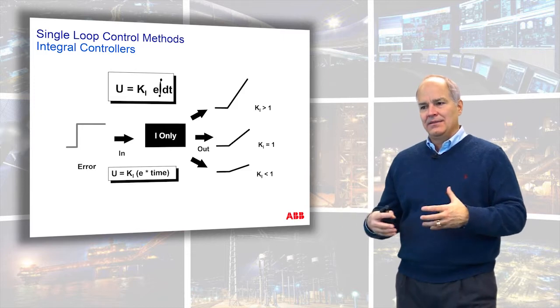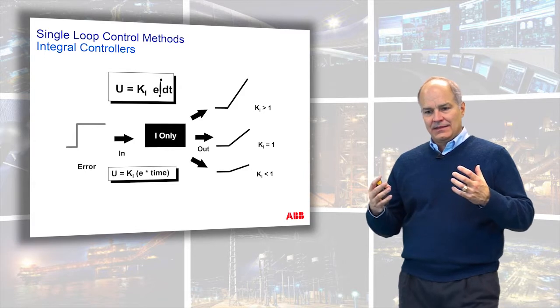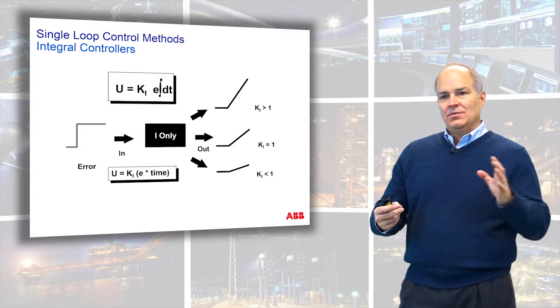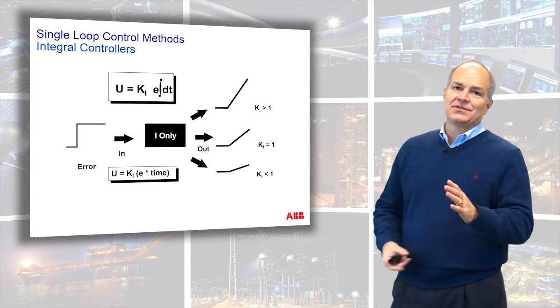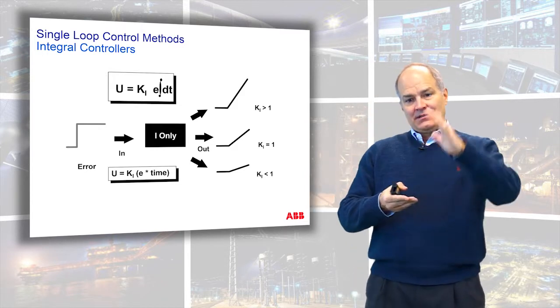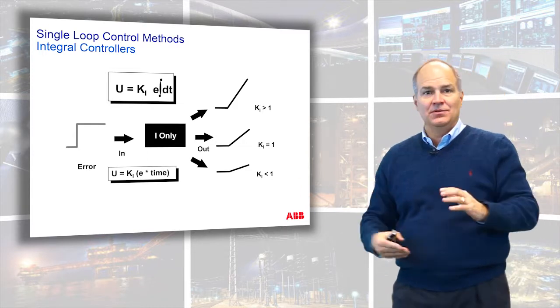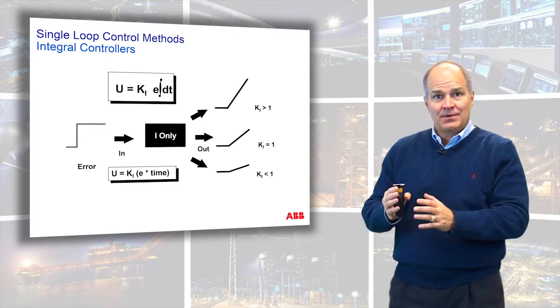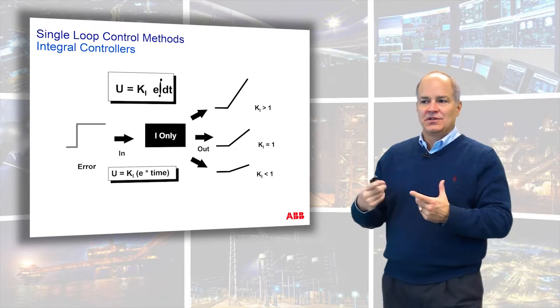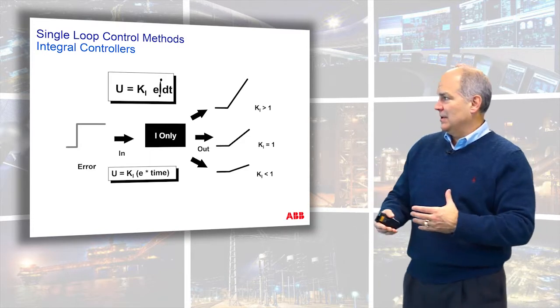The integral gain relates to the mass of the device. If you have a heavy device, you don't want the output to move faster than the device can respond, otherwise the output changes faster than the process can move — called windup. If you have a light process, you can get away with zeroing the error faster. So the integral time relates to how fast the process can move, which is typically defined by the time constant.